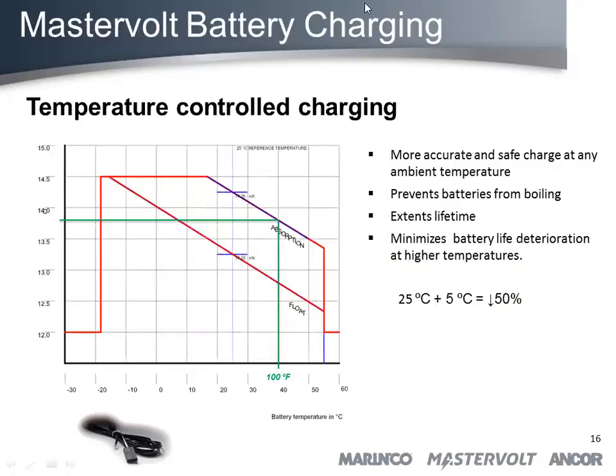Now take an example. It's not uncommon in Florida that in the summertime it's 100 degrees in the engine room, right? So look at 100 degrees Fahrenheit, what that absorption voltage is. You're looking at 13.8 pretty much. If you did not have that temperature sensor plugged in, you would have been at 14.25. That means you're overcharging the battery by more than half a volt. That's why it's so important to have that temperature sensor connected. Another thing is that the temperature sensor also cuts off the charging voltage when you're exceeding 55 degrees C or when you get under -20. It's very tricky for batteries to charge them outside those two parameters. Does it make sense?